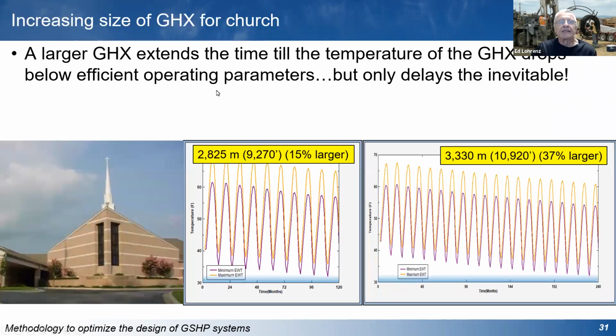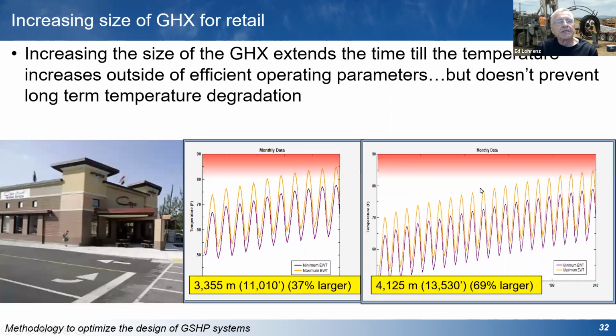And really, increasing the size of the ground heat exchanger doesn't help. It delays the inevitable drop in temperature in the church. Even if the system is larger than the 8,000 feet that the rules of thumb would suggest, it's still going to drop in temperature over time. Retail store, exactly the opposite. Even if we make the ground heat exchanger 69% bigger than the rules of thumb, you're still going to get there after about 20 years.